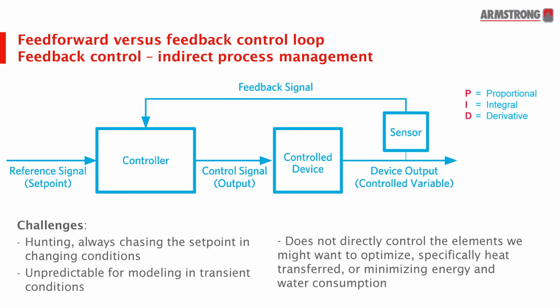I need to open a chilled water control valve, let more chilled water into the space to help keep the people in the space comfortable. So that's a feedback control loop. It's not directly analyzing the process that's being controlled, but it tends to work. There's a little bit of hunting and drift that occurs over time, and we've learned how to tune that so that we minimize that hunting and that error as it tries to hit set point.